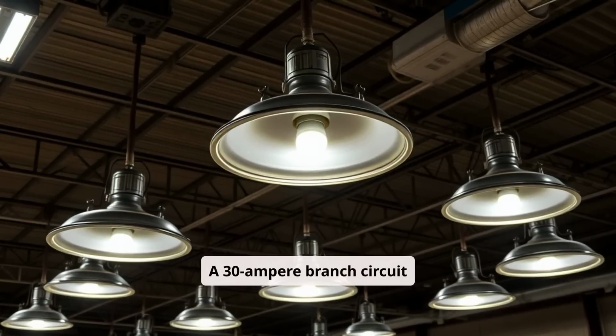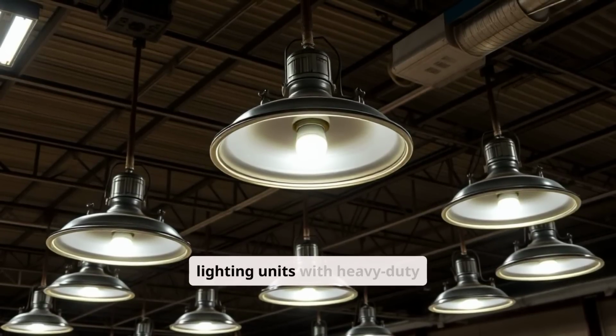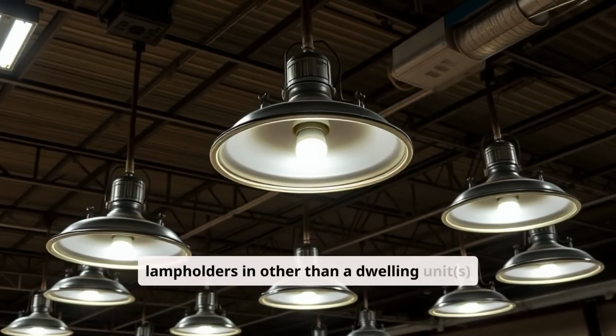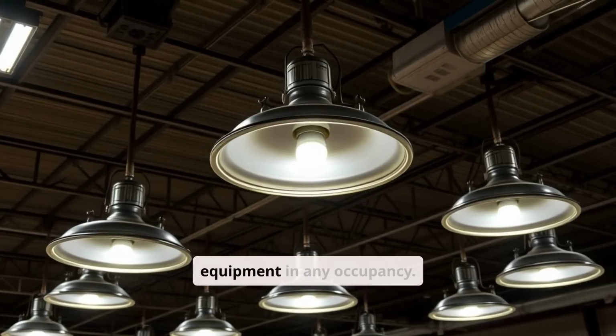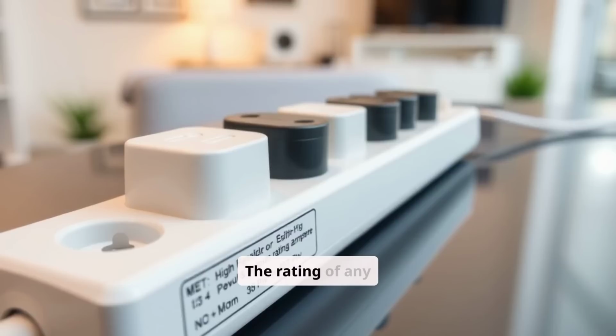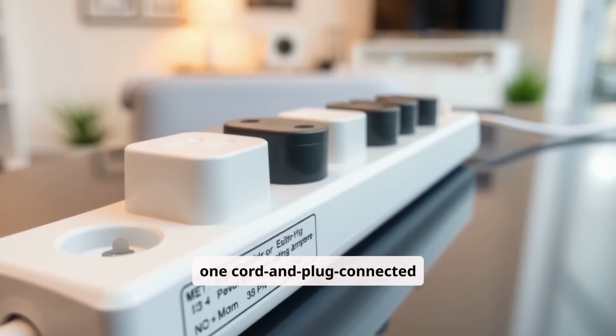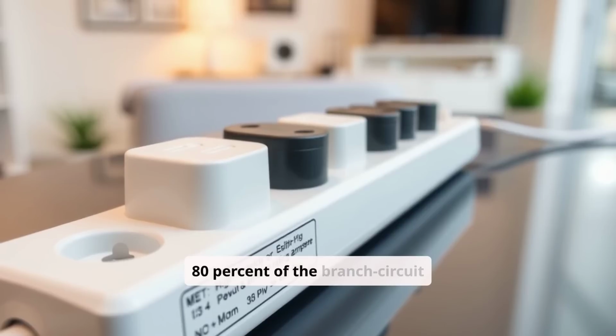A 30 ampere branch circuit shall be permitted to supply fixed lighting units with heavy-duty lamp holders in other than a dwelling unit, or utilization equipment in any occupancy.